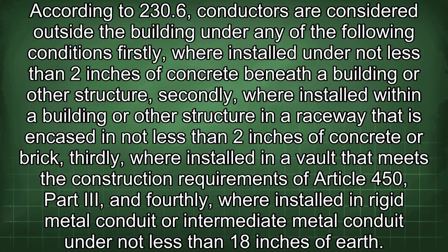Firstly, where installed under not less than 2 inches of concrete beneath a building or other structure. Secondly, where installed within a building or other structure in a raceway that is encased in not less than 2 inches of concrete or brick. Thirdly, where installed in a vault that meets the construction requirements of Article 450, Part III. And fourthly, where installed in rigid metal conduit or intermediate metal conduit under not less than 18 inches of earth.